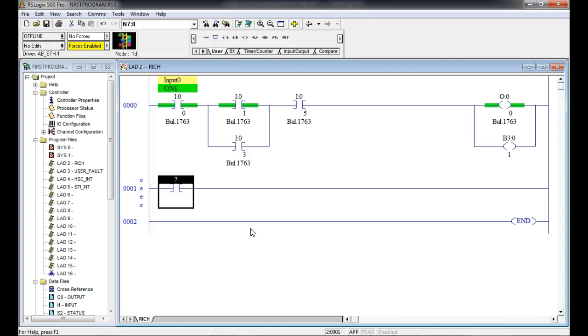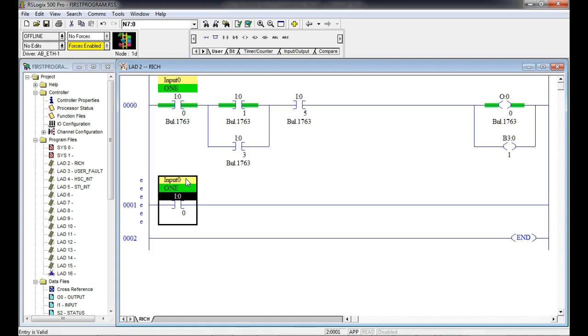Yeah. So notice what I'm going to do here. I'm going to come up here, click on that, and type in 1. Can y'all see what it did? It automatically inserted the comment and the address for me. So that's the power of symbols. In your new PLCs, they don't call them symbols anymore, they call them tags. So your new PLCs basically require symbols. But what you do is you go ahead and assign all these symbols, and from then on you're not dealing with numbers, you're just dealing with what? Names, yeah.